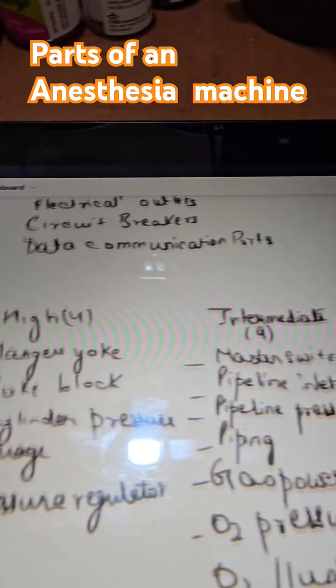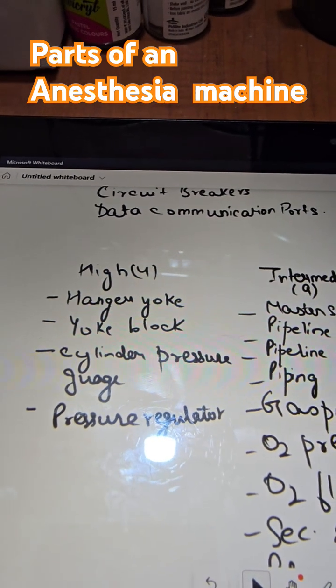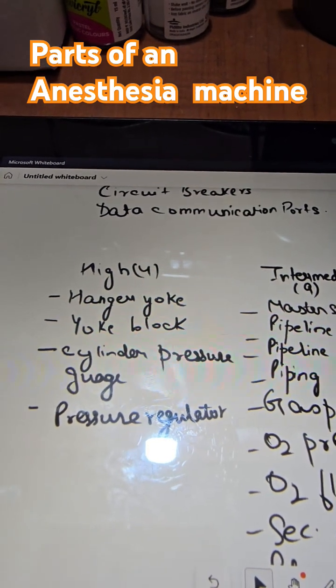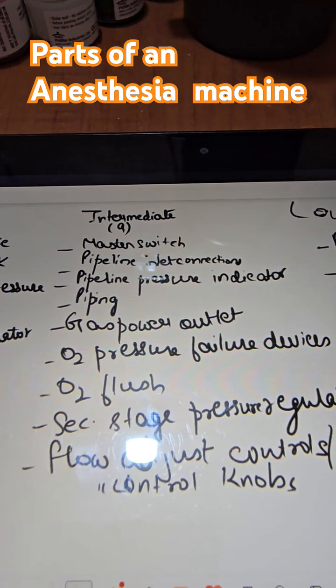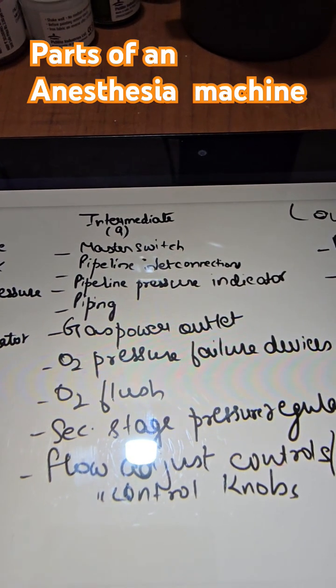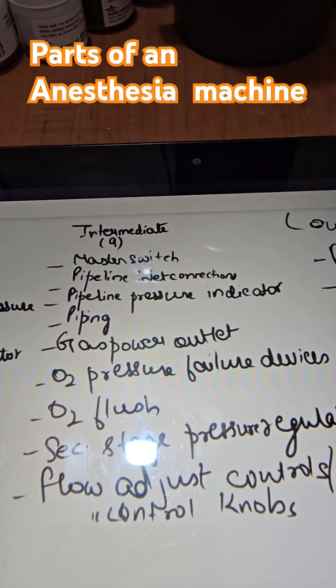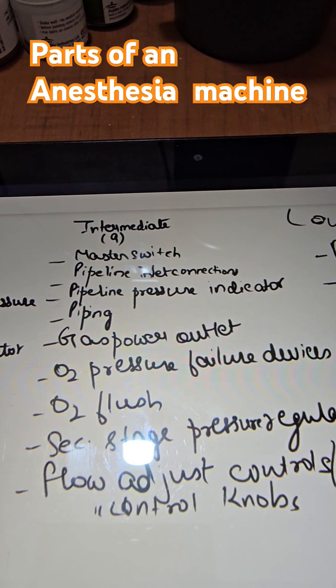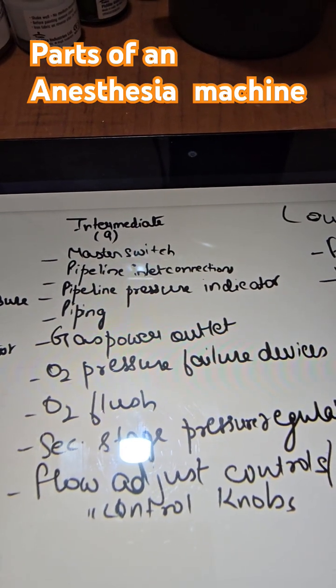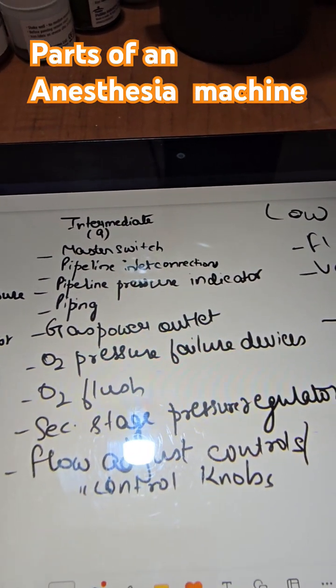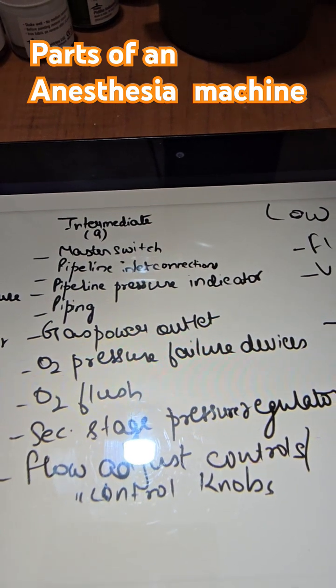The pneumatic part is further divided into high, intermediate, and low pressure systems. The high pressure system contains the hanger yoke, yoke block, cylinder pressure gauge, and pressure regulator. The intermediate pressure system consists of the master switch, pipeline interconnections, pipeline pressure indicators, piping, gas power outlet, and oxygen pressure failure devices.